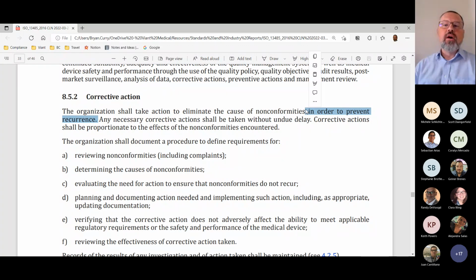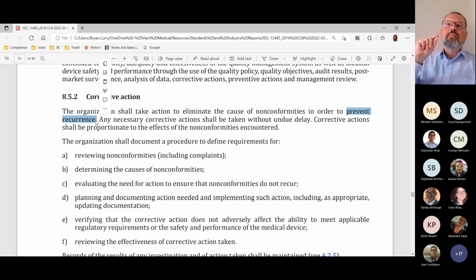And you can still make the argument that you prevented a significant amount of recurrence and that the remaining probability of recurrence is in line with your risk management documentation and is considered acceptable by the design. Now, ultimately, in our circumstance, the customer is largely going to be the one that makes the determination that any residual occurrence rate is acceptable. But just know that that is a defensible position within your corrective action program.